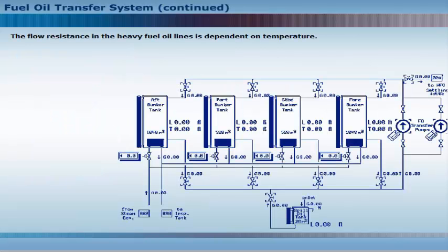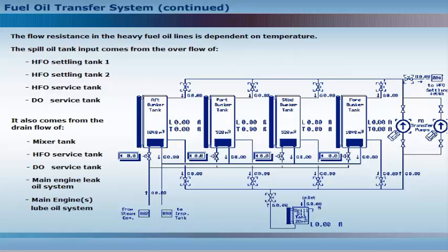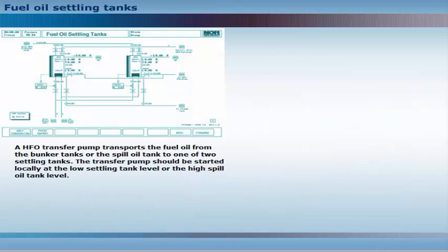The flow resistance in the heavy fuel oil lines is dependent on temperature. The spill oil tank receives input from the overflow of heavy fuel oil settling tank number one, settling tank number two, heavy fuel oil service tank, and diesel oil service tank. It also comes from the drain flow of the mixer tank, heavy fuel oil service tank, diesel oil service tank, main engine leak oil system, and main engine lube oil system. A heavy fuel oil transfer pump transports the fuel oil from the bunker tanks or the spill oil tank to one of two settling tanks.